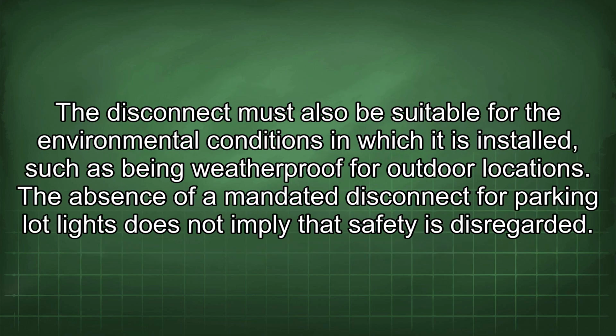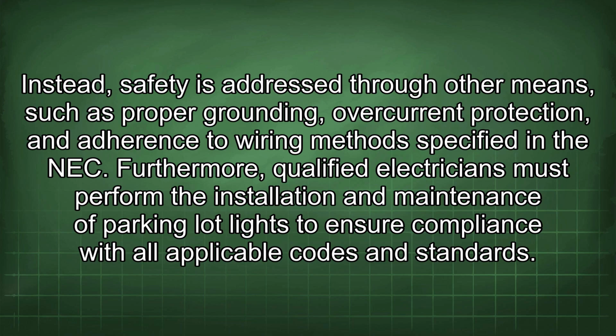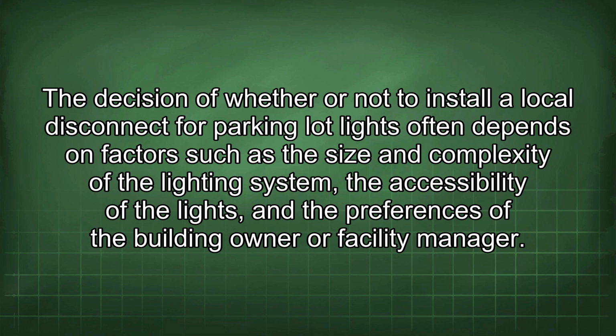The disconnect must also be suitable for the environmental conditions in which it is installed, such as being weatherproof for outdoor locations. The absence of a mandated disconnect for parking lot lights does not imply that safety is disregarded. Instead, safety is addressed through other means, such as proper grounding, overcurrent protection, and adherence to wiring methods specified in the NEC. Furthermore, qualified electricians must perform the installation and maintenance of parking lot lights to ensure compliance with all applicable codes and standards. The decision of whether or not to install a local disconnect for parking lot lights often depends on factors such as the size and complexity of the lighting system, the accessibility of the lights, and the preferences of the building owner or facility manager.